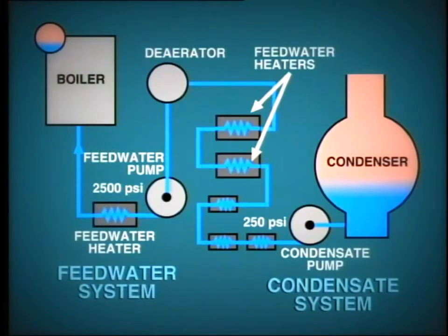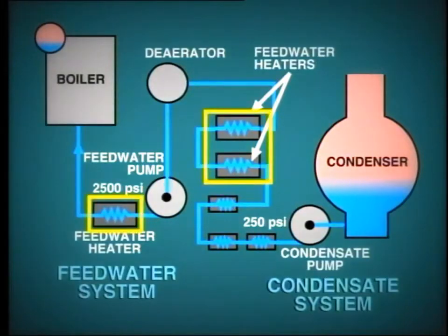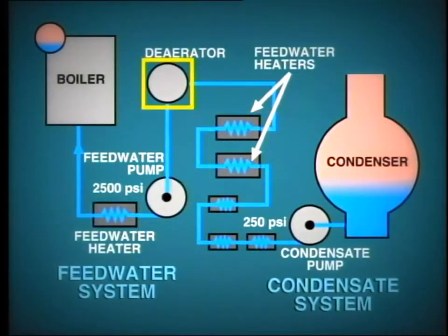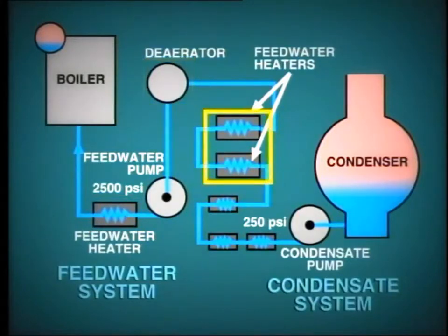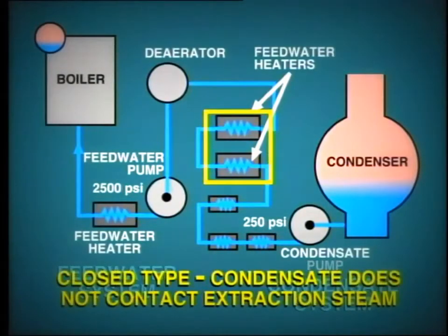There are two basic types of heat exchanger used in the feedwater system, that is, the closed type and open type. For example, the two low-pressure heaters shown here are of the closed type, meaning that the condensate passing through the heater does not come into contact with the extraction steam which is providing the heat.